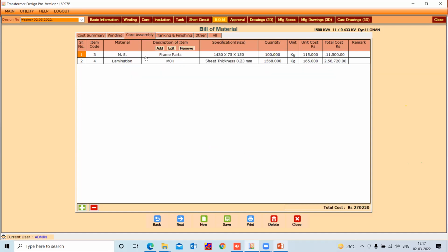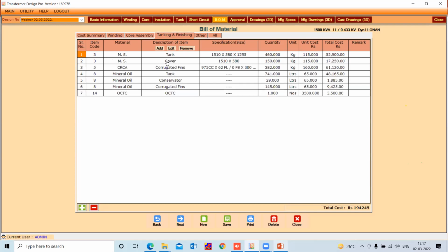Next is the core coil assembly detail. So MS frame part related information, including the sizes of frame parts, thereafter the lamination information, the core grade and thickness of grade, quantity, and the unit cost and total cost. Thereafter tank and fitting accessories. You will get the tank weight separately, cover weight separately, corrugated fins weight with the sizes, then the oil in tank, conservator and corrugated fins, and the OCTC price is available to edit or manipulate here. Thereafter, in the bottom left hand side corner, plus and minus buttons are available to add more rows or delete some items. This is the way you can add more items here also.